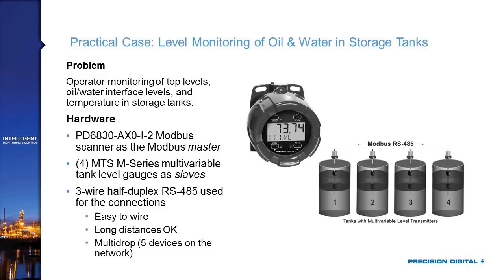Here's a practical case study. An operator wants to monitor the top level, the oil-water interface level, and the temperature of liquid stored in storage tanks — at a transfer terminal or separator facility. Oil and water mix and then separate when left to settle. They're going to use a PD6830X Modbus Scanner as their master device — the only display device needed for this setup — and four MTS M-Series multivariable tank level gauges as slave devices.